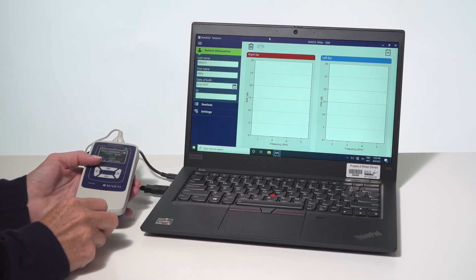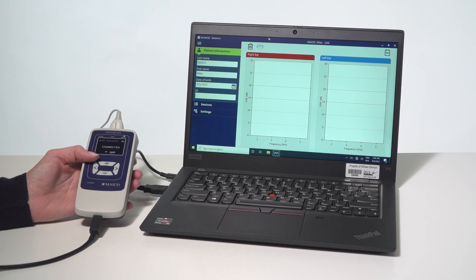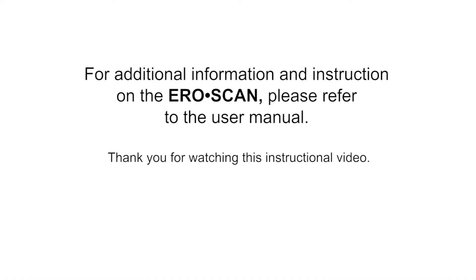To transfer test results from the MAICO device, enter in the patient information. Upon completion or selecting transfer result, transferring occurs. For additional information and instructions on the EroScan, please refer to the user manual. Thank you for watching this instructional video.